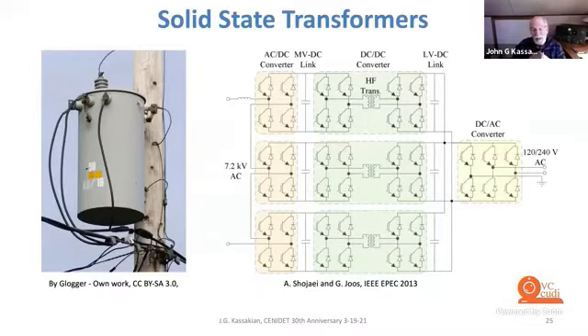Another fascinating area, one which is only slowly beginning to have an impact, is solid-state transformers. The transformer you see on the left is a transformer on a utility pole that converts something like 7 kV down to the voltage used by residences - in the US, 120 or 240 volts, 60 hertz. That's a very inexpensive device. You can weigh it, and then you know how much it costs by the pound, because it's mostly iron and copper.